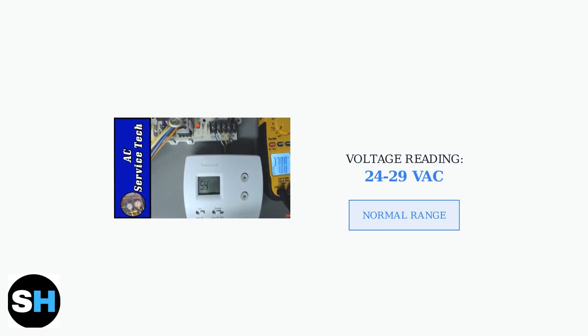If you don't have a C wire, you may need a power extender kit. Use a voltmeter to test the voltage between the RC and C wires at the Ecobee terminals. The reading should be between 24 and 29 volts AC for proper operation.